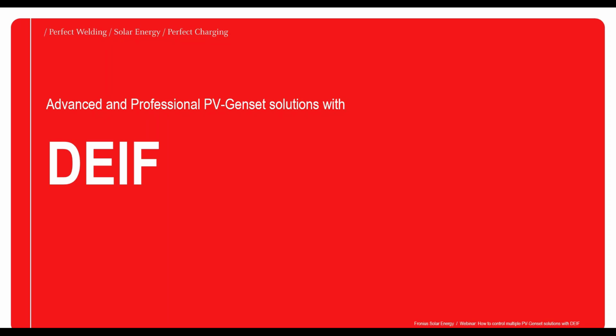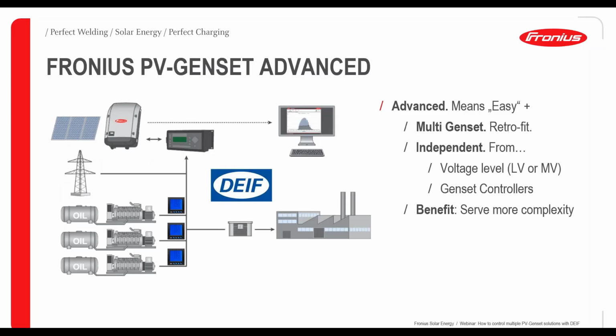Okay, so before switching over to Ellen for the presentation, I quickly want to mention what we will see in the next slides. Ellen will be talking about the advanced and professional solutions. What is the difference actually? With the advanced solution, we have all the benefits that we have with the easy solution, but now it is possible to serve more complexity, in that we can have multiple diesel generators within the system. It can be retrofit, so it's not dependent on the manufacturer or the brand of the diesel generators. We are also independent from the voltage level, low voltage or medium voltage, whilst with the easy solution only low voltage is possible. The overall benefit is that we can serve more complexity.